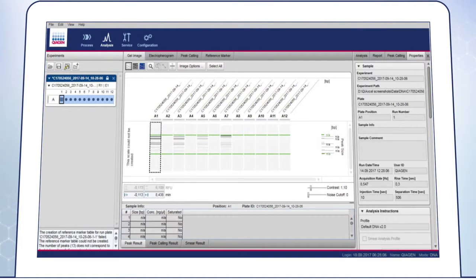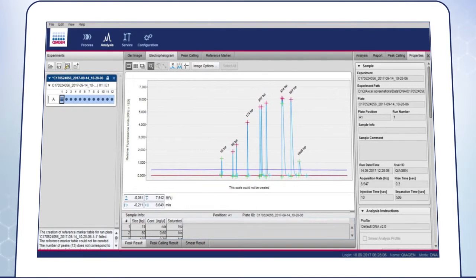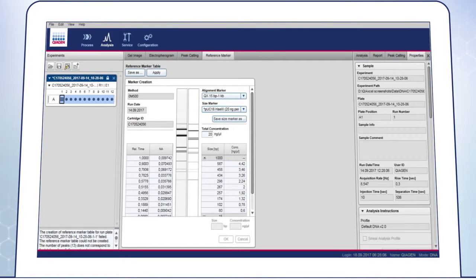To see the peak positions, go to the electropherogram view. Here the peaks can be seen in more detail. Under the reference marker table, when selecting the size marker position, the reference marker can be created and saved. If not yet done in the profile when starting the run, insert the size marker type and total concentration. Click on Apply to implement the size marker to obtain the concentrations and size calculations.